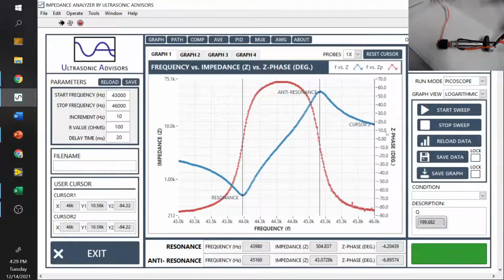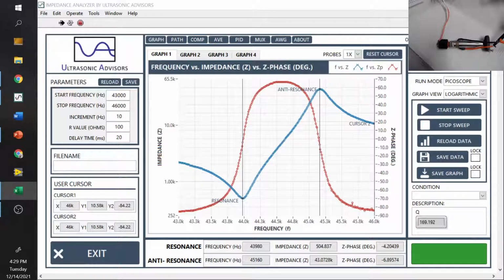All right, and I'll press this button here. So I got to 169. I'm going to type in all of these as we go. I have another screen here. We're going to call this the transducer with stiff, with high pressure, so we'll distinguish that. The frequency now is 43.998. So it seems to be increasing as I clamp down. Actually, I'd say 44.0. The quality factor is 169, and the impedance is 504. So here we go. And I'm just going to throw that here.